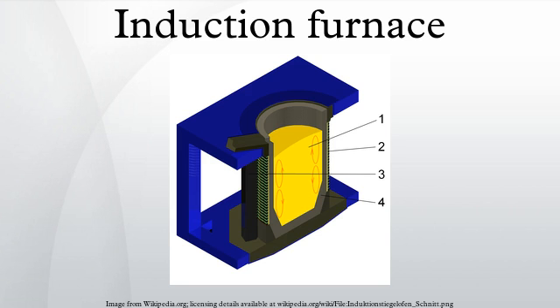This is due to the skin depth which is a measure of the distance an alternating current can penetrate beneath the surface of a conductor. For the same conductivity, the higher frequencies have a shallow skin depth that has less penetration into the melt. Lower frequencies can generate stirring or turbulence in the metal.